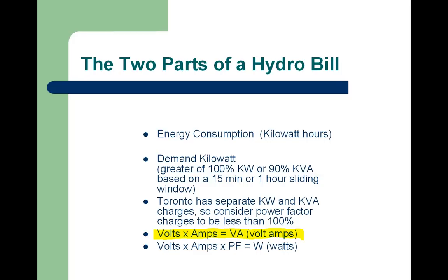So if you start two large compressors within a minute or so of each other, it's really not going to affect your peak demand for a month, because it's actually averaging over a 15-minute period. So whether you turned on two 100 horsepower compressors within a minute of each other or within 3 minutes of each other, the overall peak inrush current that a compressor would draw would not be seen on the demand component of your hydro bill.